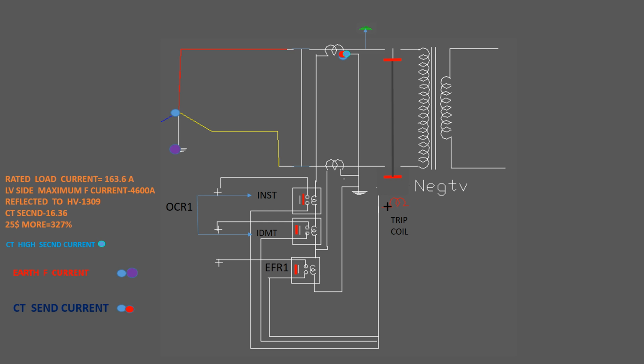Here we have taken two relays, instantaneous and IDMT, for overcurrent protection, but in the microprocessor relay, the two CT outputs are given to the microprocessor relay, and it does all these things through the program. But in the electromechanical relay, we have to design the circuit. In the microprocessor relay, we have to program the situation.